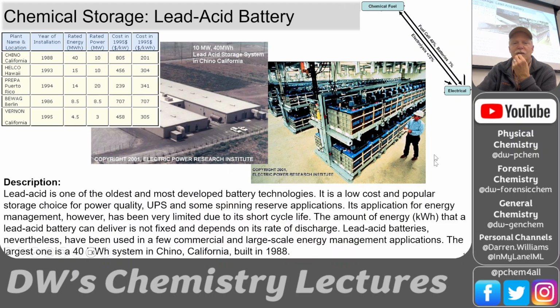Then there's the tried and true lead acid battery. We know lead acid batteries work - they're not technically difficult to make, and they charge and discharge pretty well. Here's one in California, a 10 megawatt battery storage facility. Here's a worker so you can see the scale of the facility. There's a lot of sulfuric acid in that building. These lead acid batteries are a lot bigger than your automobile batteries because they're made for power applications.